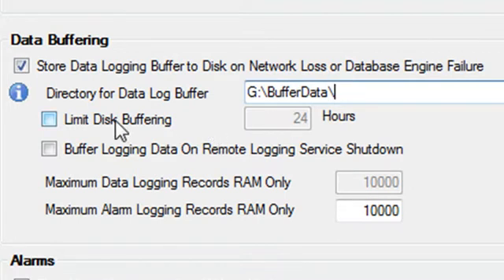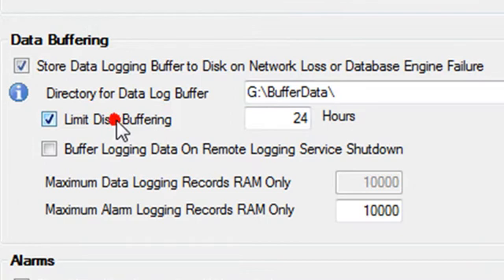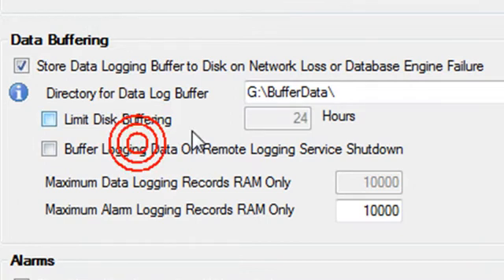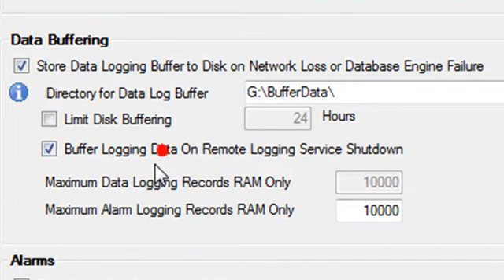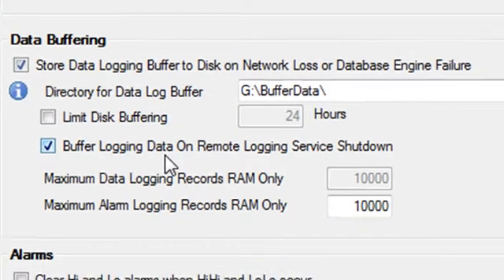If you want to limit the data buffering to a particular time period, you can enable the property limit disk buffering. If you'd like to buffer data at the data source when a remote data logging service is stopped, you can enable the property buffer logging data on remote logging service shutdown.